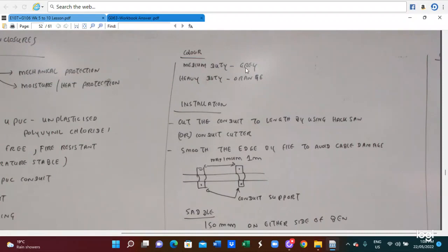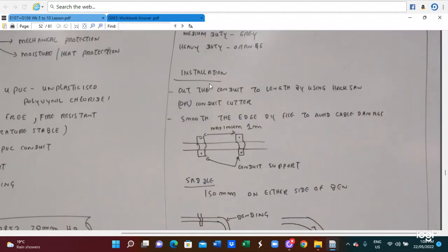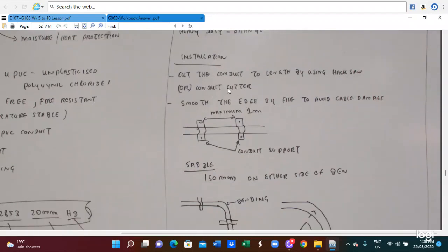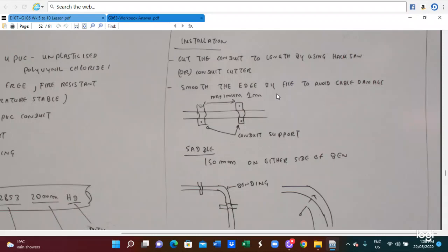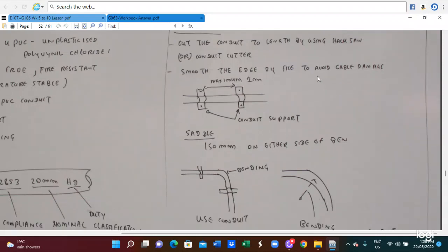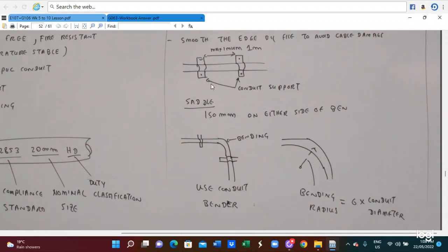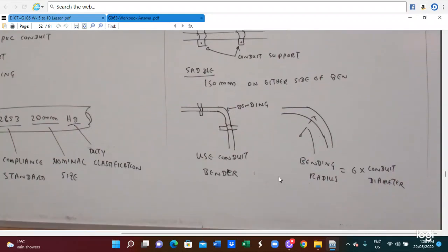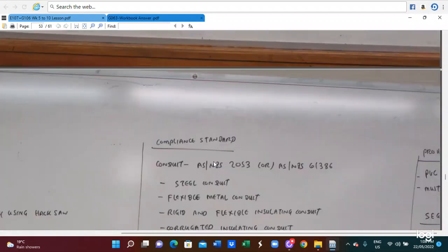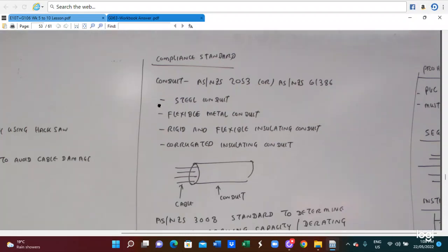The color can be the medium duty is gray, heavy duty is orange. Installation method is that we have to cut the conduit. Tools are by using a hacksaw and a conduit cutter and a smooth edge, to avoid damage to the cable. And we have to use a saddle and also the bending system. So bending is, when you bend it, there will be the radius 6 times of conduit diameter.